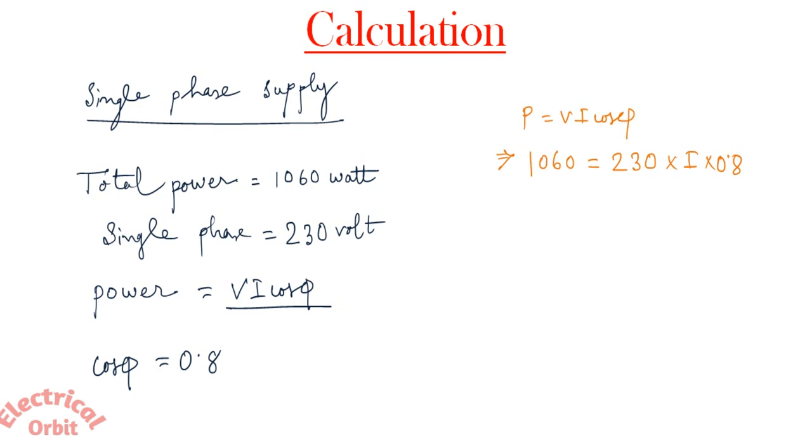In case of MCB rating, as I have said earlier, the rating will be solely on the value of current. Our main objective is to determine the value of the current so that we can determine the rating of the MCB. So here the value of the current we determined is 5.76 ampere.